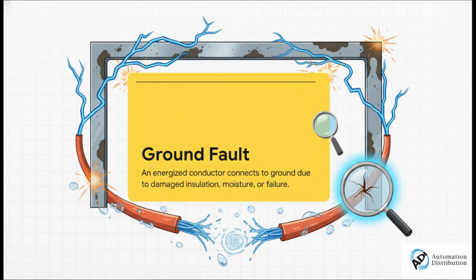And finally, there's the ground fault. This one is, well, it's a little sneakier. This happens when electricity basically leaks out and goes somewhere it shouldn't, like the metal enclosure of the panel. It could be from a frayed wire or a little bit of moisture. It might not be that massive current spike, which actually makes it harder to detect, but it poses a huge risk to anyone who touches that panel.